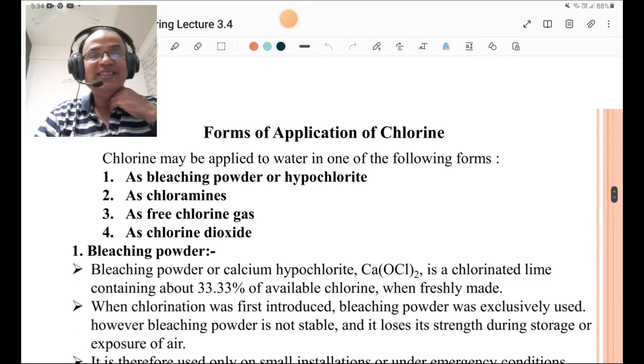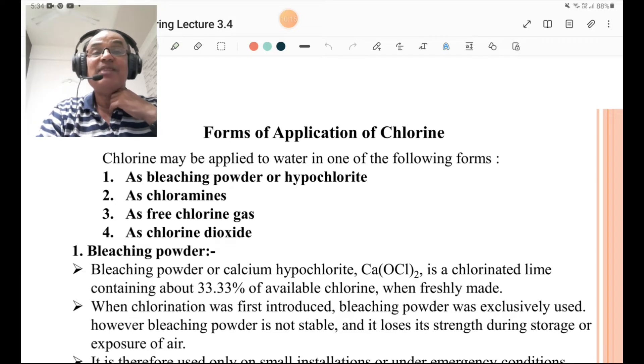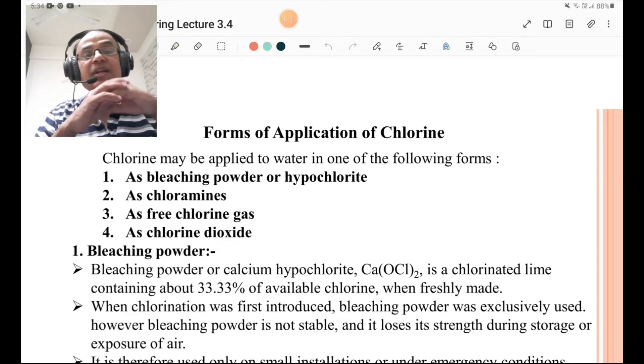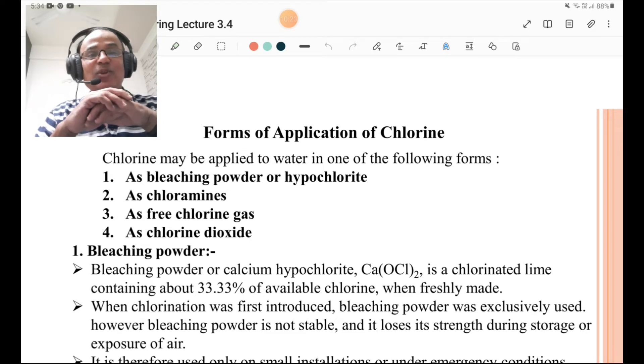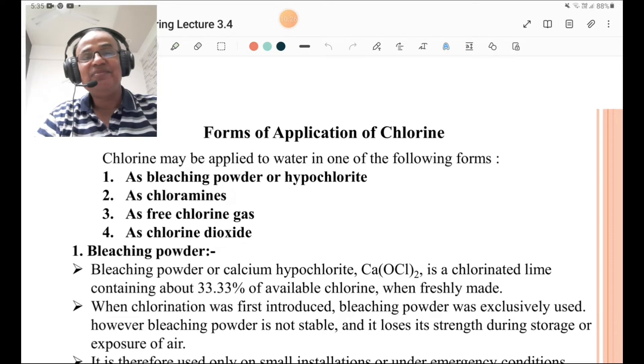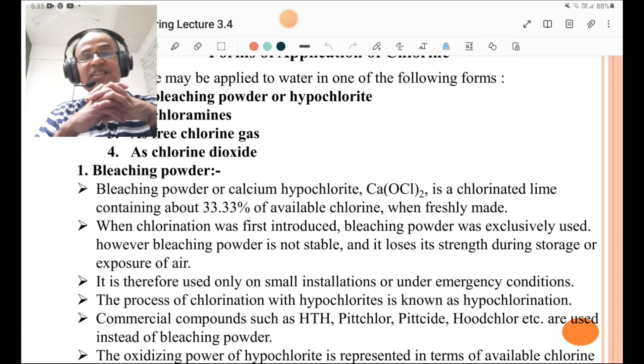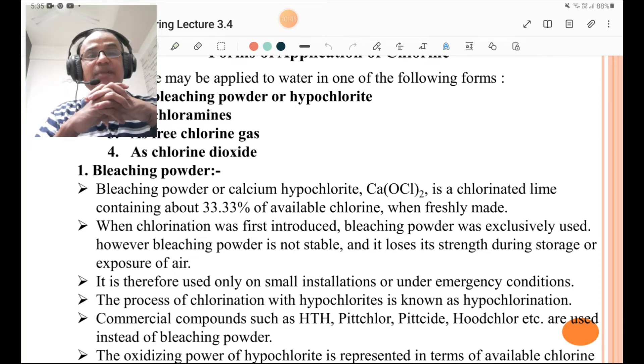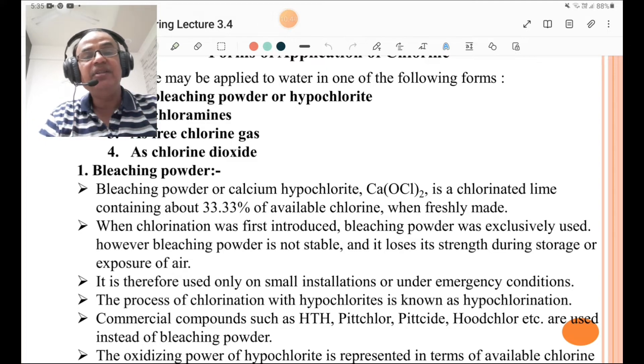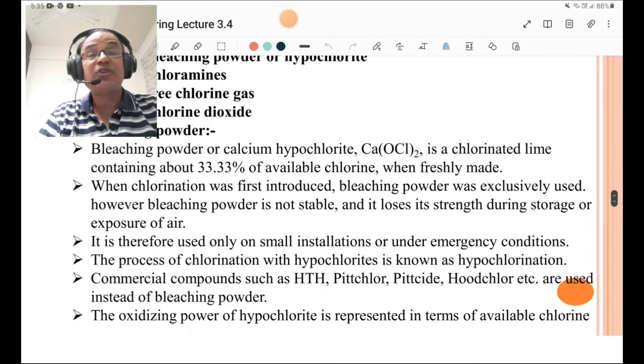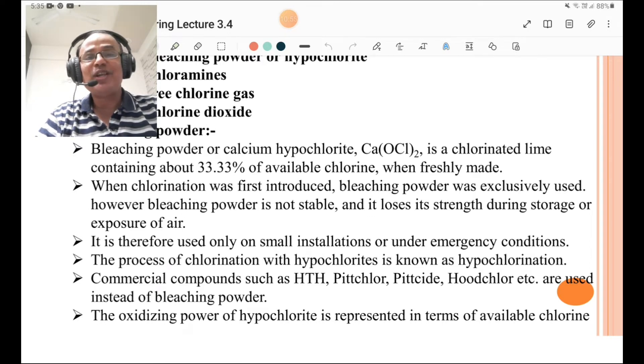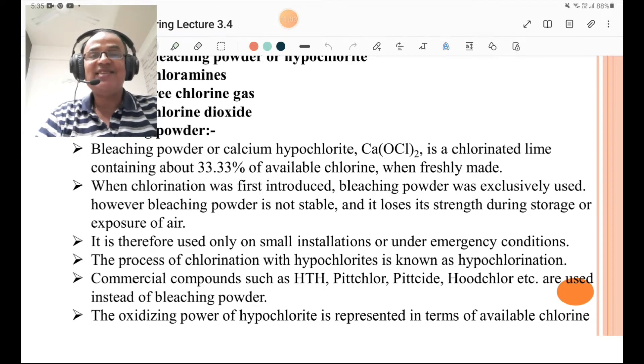Forms of application of chlorine: chlorine may be applied to water in the following forms — first, as bleaching powder or hypochlorite; second, as chloramines; third, as free chlorine gas; and fourth, as chlorine dioxide. Bleaching powder, or calcium hypochlorite, is chlorinated lime containing about 33.33% available chlorine when freshly made. When chlorination was first introduced, bleaching powder was exclusively used. However, bleaching powder is not stable as it loses its strength during storage or exposure to air, and is therefore used only on small installations or under emergency conditions.